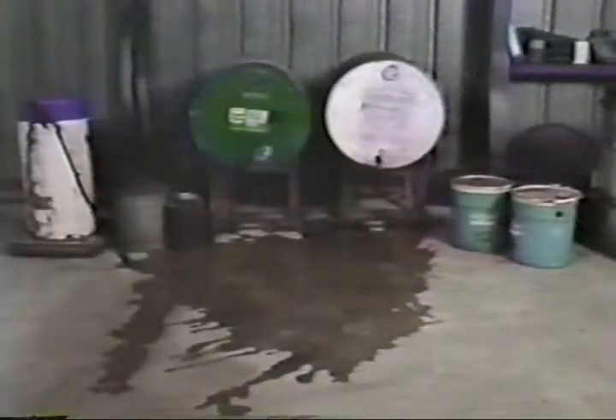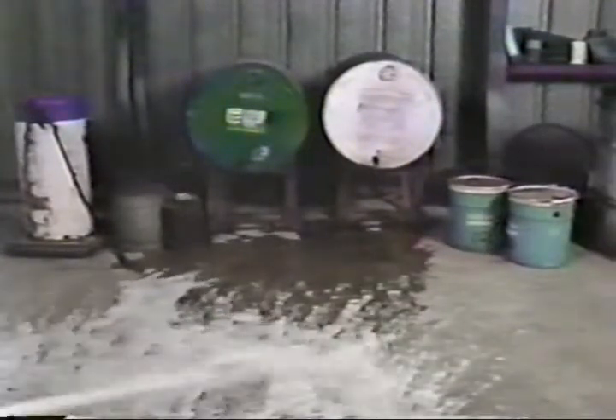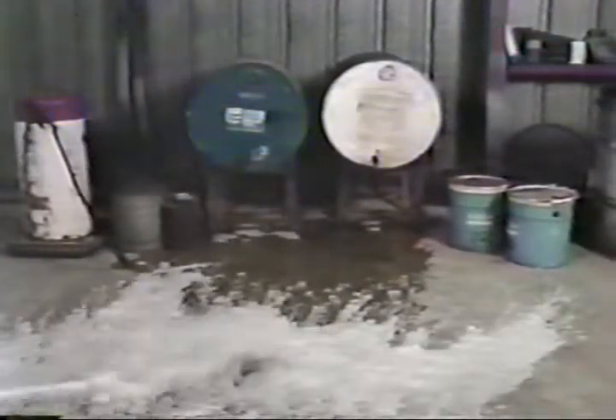If you are unable to play the foam off the back wall, you can spray the foam directly into the liquid. It's important, however, to momentarily divert the stream so that the foam blanket can seal itself and completely cover the liquid. Another method for open container fires is to stand back and lob the foam so it falls over the fire. AFFF extinguishers are also used to prevent fires on flammable liquid spills. The foam blocks the release of vapors, preventing ignition.